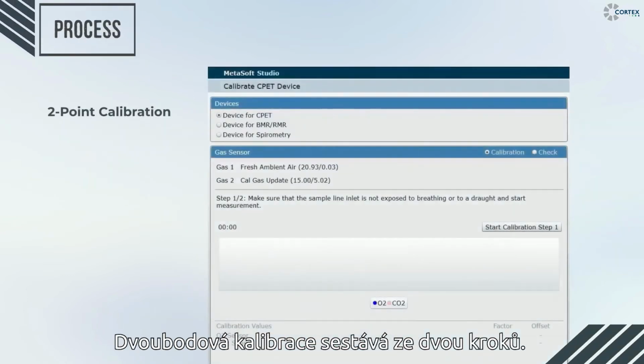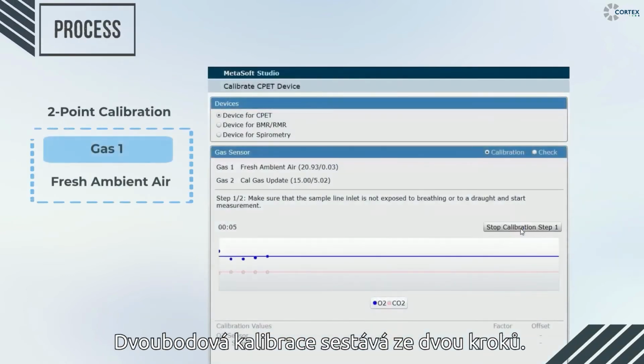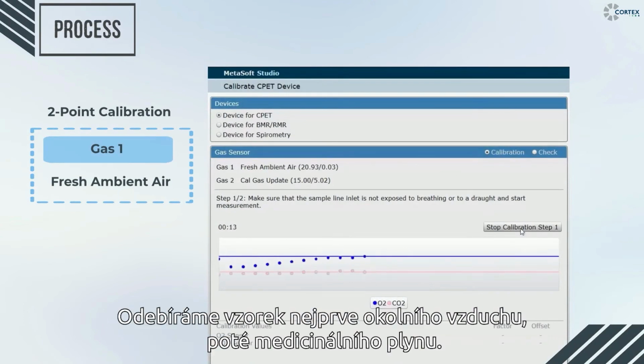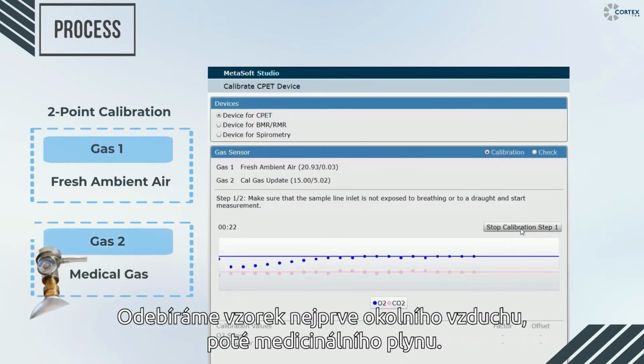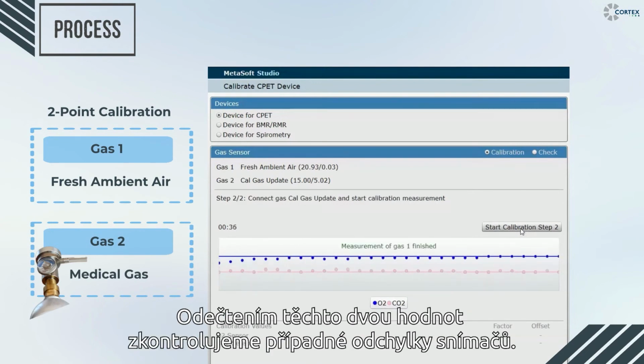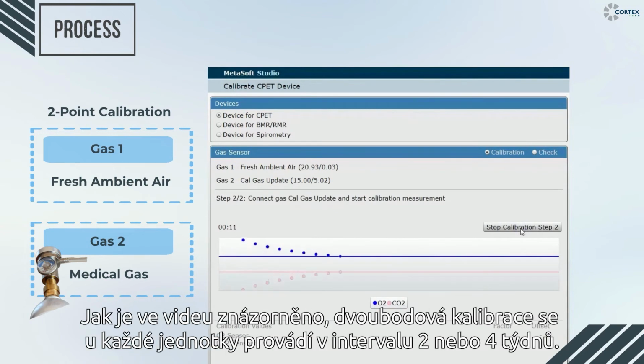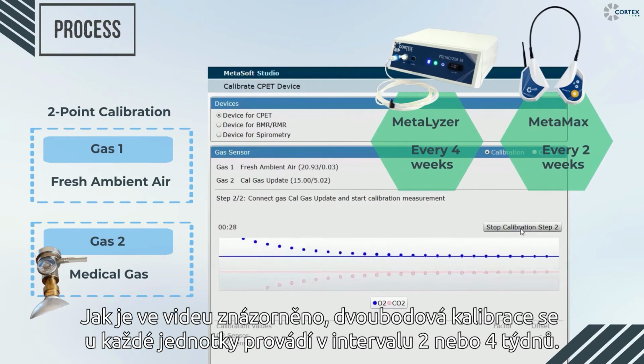The 2 point calibration consists of 2 steps: sampling of the ambient air and sampling of the medical gas. By reading these 2 values, we check for any potential drifts of the sensor. As depicted on the clip, the intervals of 2 point calibration are performed every 2 or 4 weeks for each respective device.